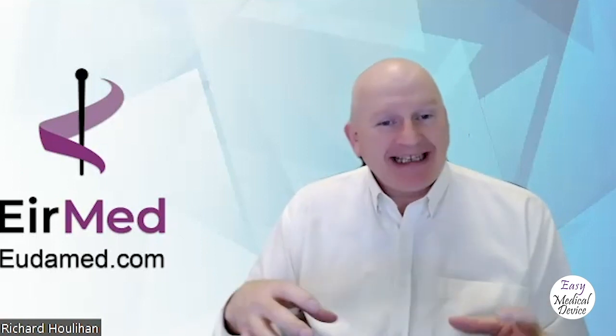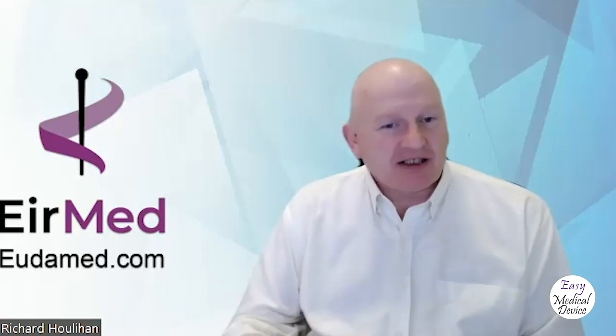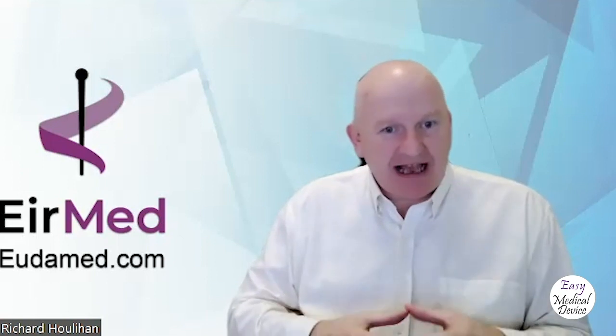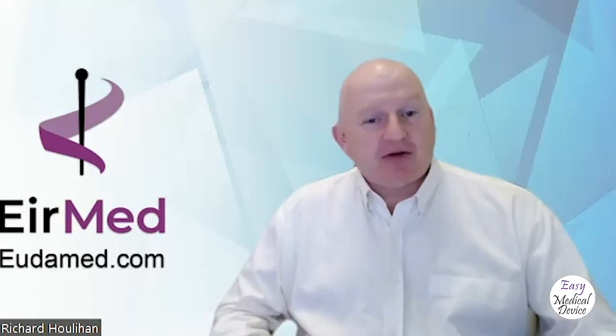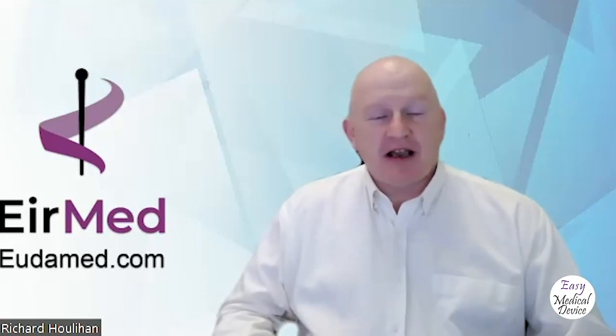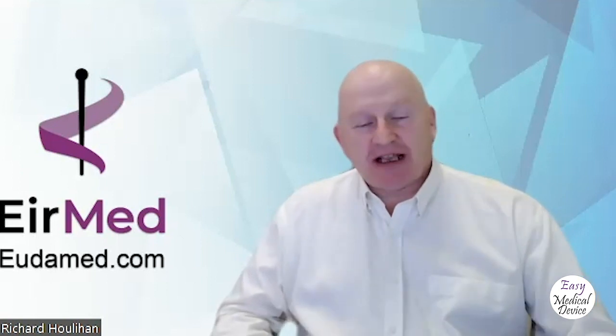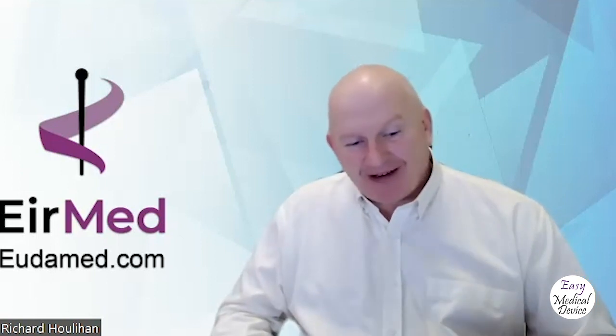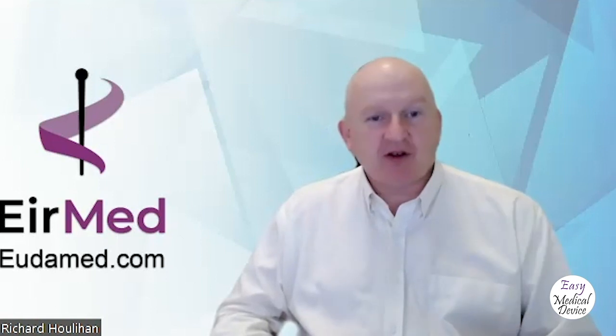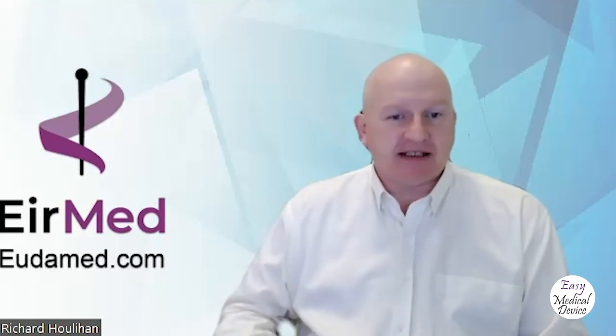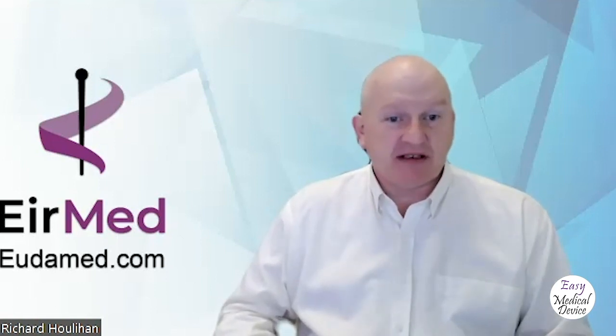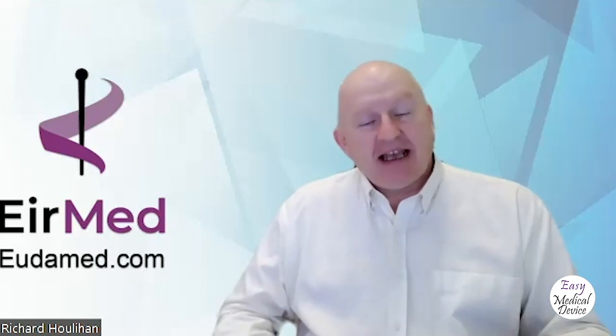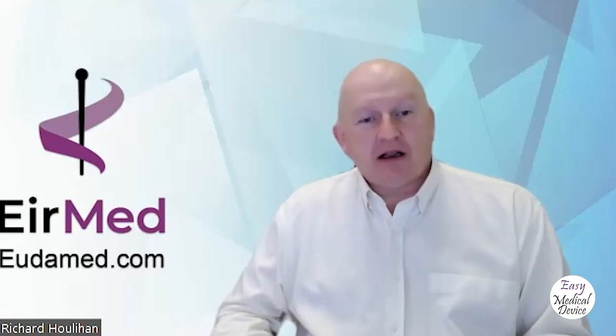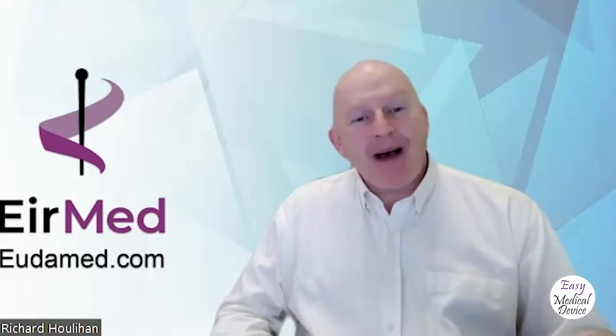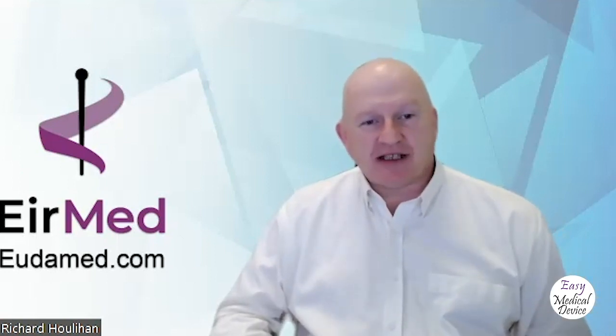But EUDAMED is the core of all the legislation. It's the piece right slap bang in the middle. If you want to comply with MDR and IVDR, you have to put your data in EUDAMED. Now, the level of data that's going in there, for those that are familiar with the GUDID system, there's like 64 data points, not all of them mandatory. EUDAMED has over 104. And of that 104, there are many where you can have multiple entries.